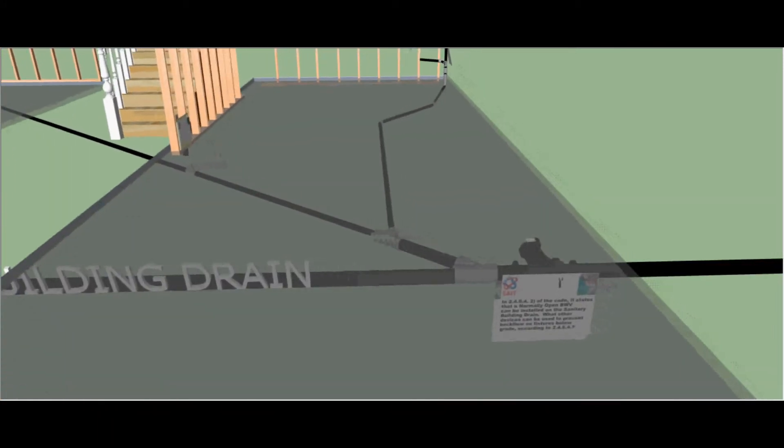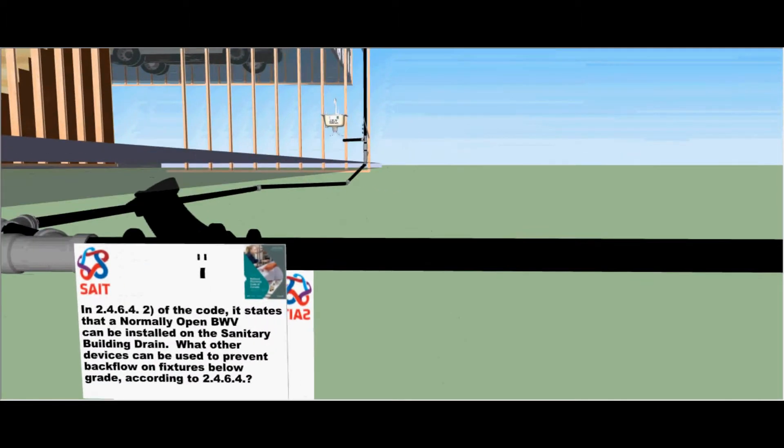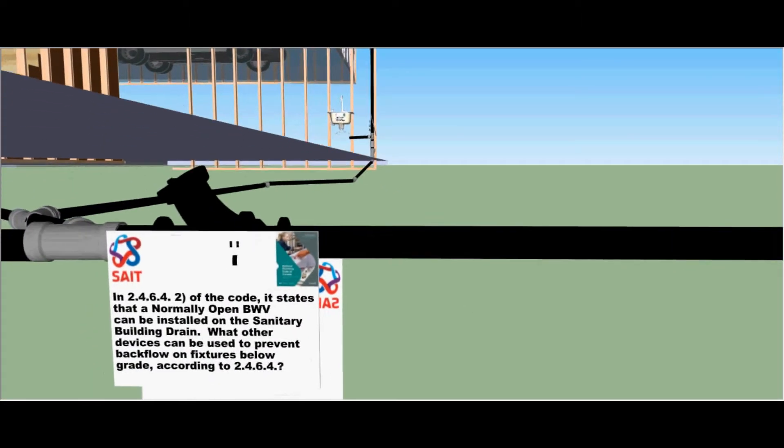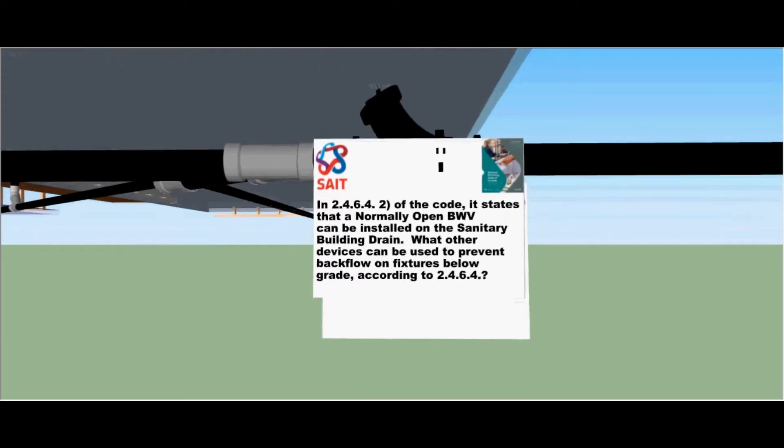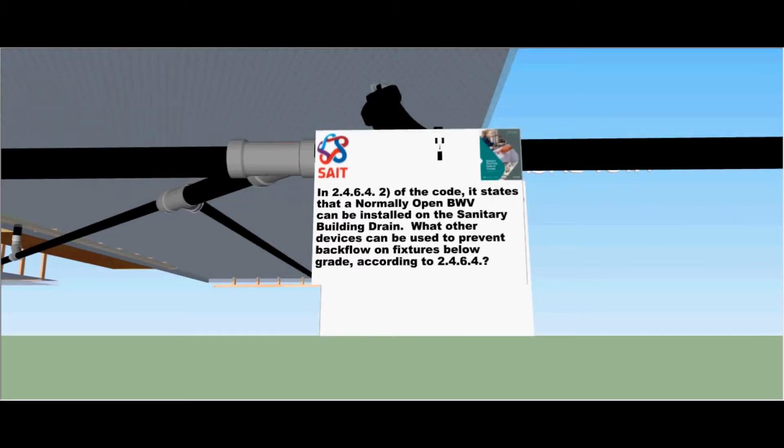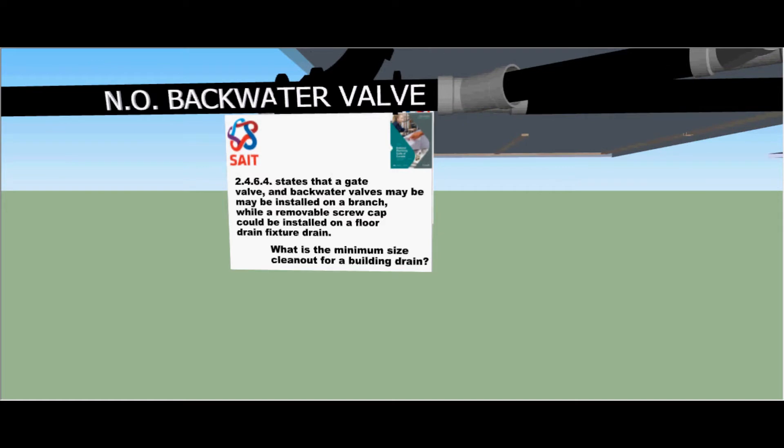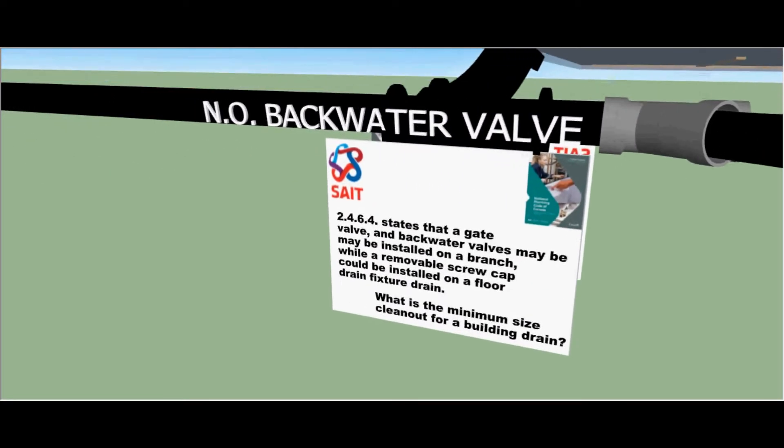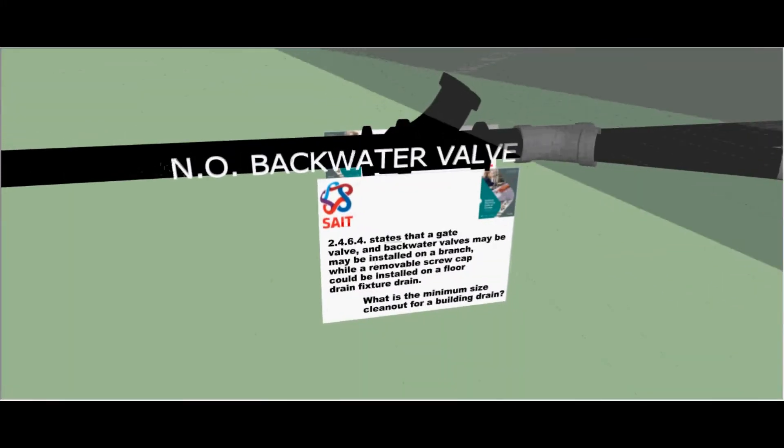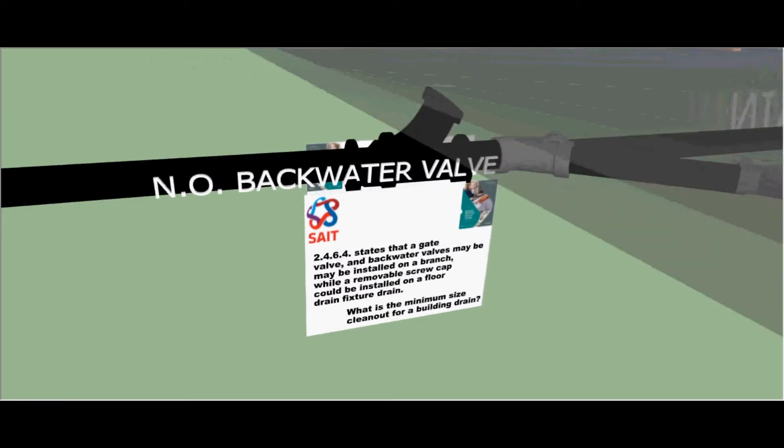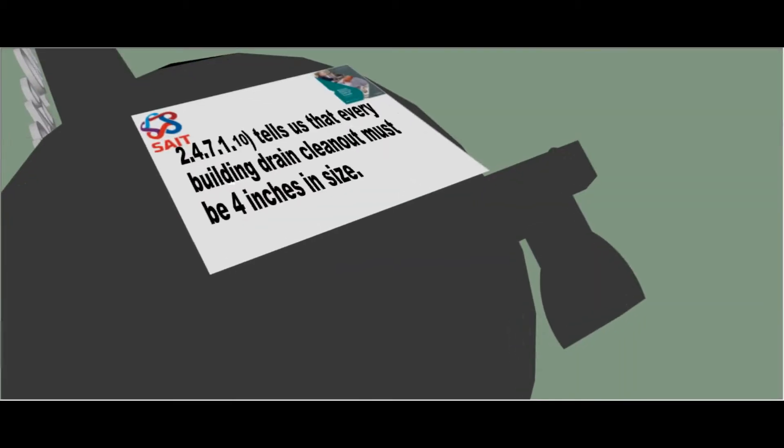Here we see the building drain and the main clean out with a normal backwater valve. It states that this backwater valve can be installed on the sanitary building drain. What other devices can be used to prevent backflow on fixtures below grade according to clause 2464? It states that a gate valve and backwater valves may be installed on a branch while a removable screw cap could be installed on a floor drain fixture drain. What is the minimum size clean out for a building drain? Clause 2471 tells you that every building drain clean out must be at least four inches in size.